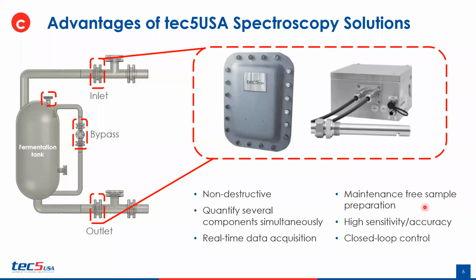Ultimately, this is a maintenance-free sample preparation. You can see on this image I've included two of our example instruments. You can locate these instruments via fiber optic probes and fiber optic cables at different locations on the process. If you want to monitor the incoming feedstock, you can essentially stick this probe into the inlet and have real-time data acquisition. You can alternatively look at measurements directly in situ within the fermentation tank, or in some bypass loop where some material is pulled from the tank and redirected back into it. And finally, if you want to look at outgoing product for quality, you can also immerse this in an outlet port. A great advantage is that you are not sacrificing too much sensitivity and accuracy when it comes to the measurement.